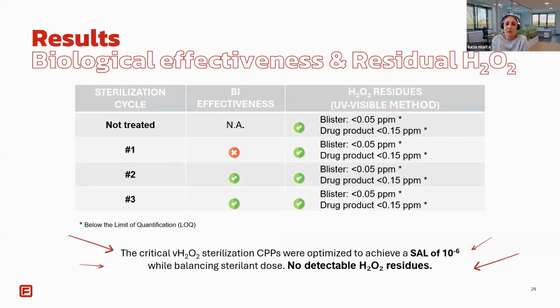In parallel, as said before, the residual amounts of H2O2 were evaluated, and as reported in the table, for both the blister and the product drug, these values are below the quantification limits. These results indicate that the selected process conditions allow us to balance the sterilization performance and the H2O2 residual control. It should be noted that these findings are based on the current test configuration and should always be confirmed under the final process conditions.